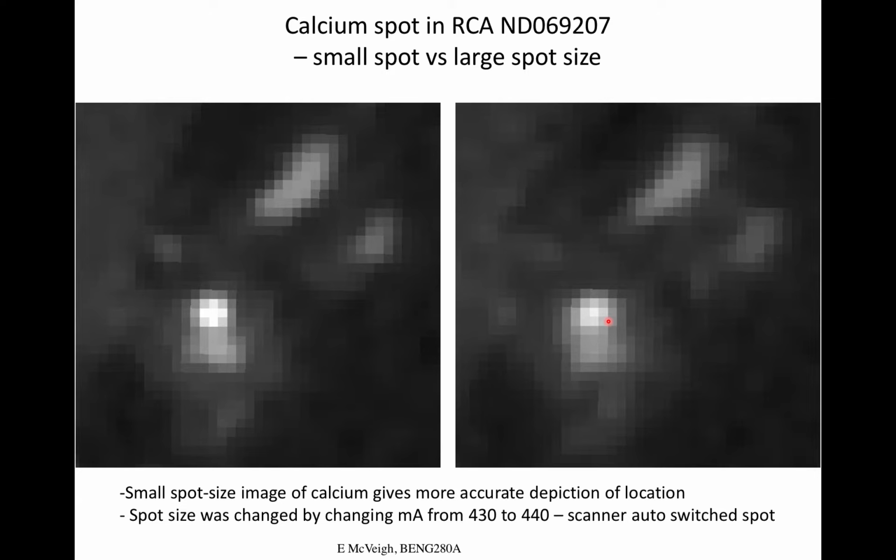It turns out in actual practice, imaging humans, because this, look at the resolution of this picture, this is the coronary vessel, right? This thing here. And so this is a really small piece of calcium, and you get this amount of broadening. It turns out this isn't a big deal in imaging human beings. So when you crank the MA up and the fact the spot size gets a little bigger, it doesn't have a huge impact on the resolution of the picture. It is lower resolution, but it's not the main thing that's going to cause you trouble.